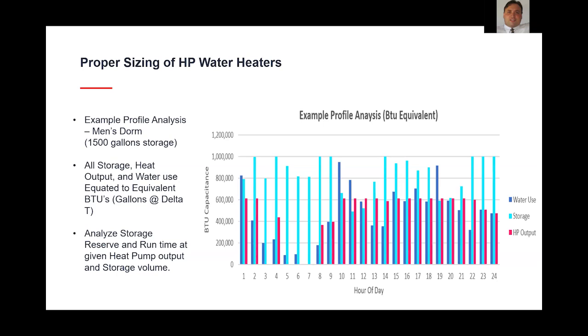And so you can convert these gallon per hour draw load rates into an equivalent BTU. You can convert the storage volume that you store at that water temperature into an equivalent BTU. And again, you're looking at this in terms of capacitance. So these loads by hour, what your starting capacitance or storage volume is, and what you have available from the heat pump water heater. And you can analyze these effects over the course of, again, typically a couple 24-hour periods, and determine, hey, am I running dangerously close to depleting my storage under any given hour? And B, do I have enough runtime? Is my heat pump sized, in sizing optimized with this storage combination to make sure that it's running enough hours out of the day?